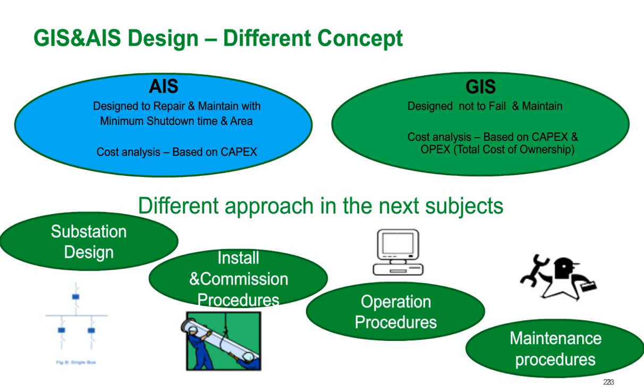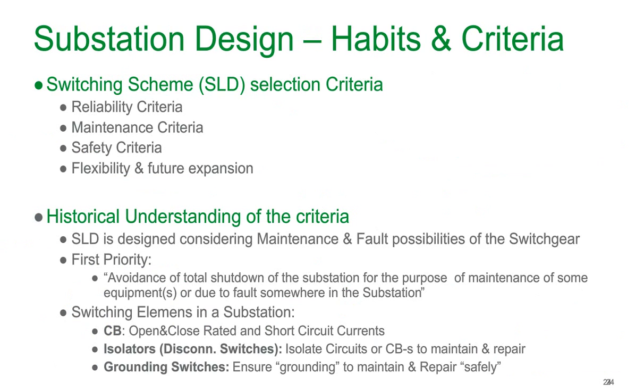All right, so with that, we'll move on. We're going to talk in the next group of slides about substation design, installation, commissioning, operation, and maintenance. So first one, substation design. I just want to talk a little bit about how you can optimize a single line, taking into account the design characteristics of GIS, because it isn't the same as metal-clad or air-insulated switchgear.